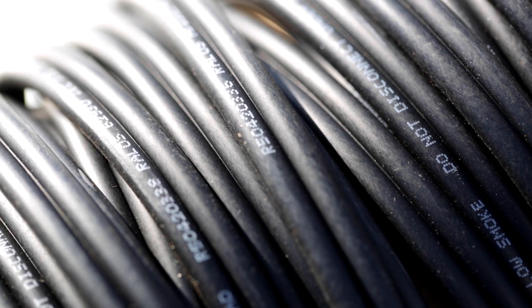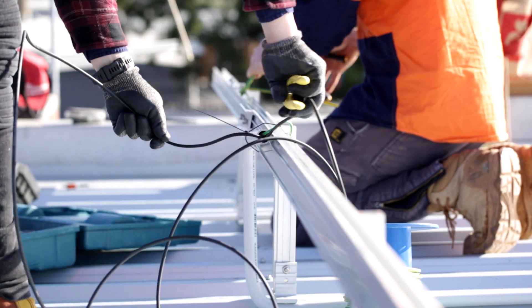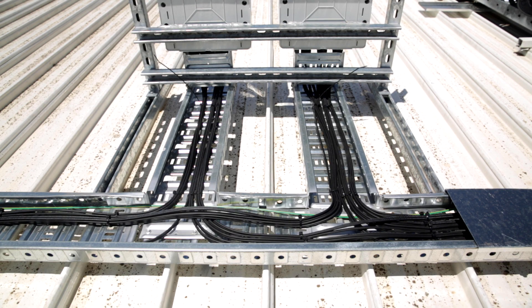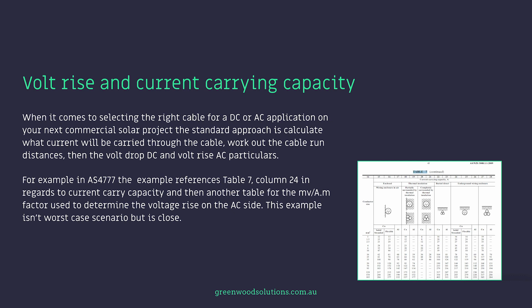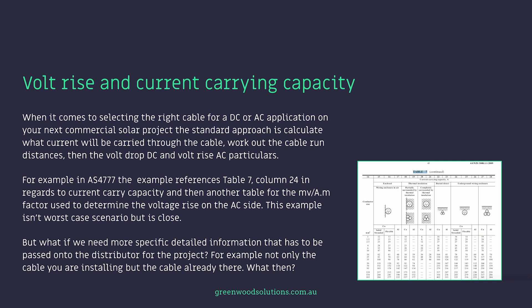When it comes to selecting the right cable for a DC or AC application on your next commercial solar project, the standard approach is to calculate what current will be carried through the cable, work out the cable run distances, then the volt drop on the DC and the volt rise AC particulars. For example, in AS4777 the reference is table 7 column 24 for current carrying capacity and another table for the millivolt per amp metre factor used to determine the voltage rise on the AC side. But what if we need more specific detailed information that has to be passed on to the distributor for the project — not only the cable you're installing but the cable already there?